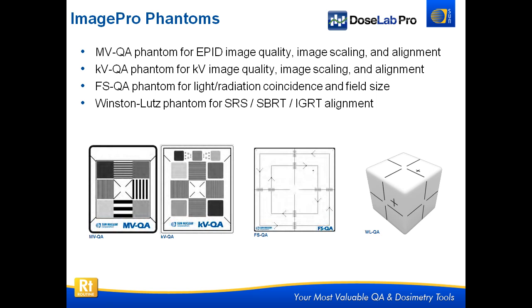We also have a Winston-Lutz Phantom for SRS, SBRT, or IGRT alignment. The cube has an embedded tungsten sphere in it. You can use it as a normal Winston-Lutz phantom, or you can do a CT scan of it, treat it just like a patient, pull it into your planning system, contour the ball as your tumor, and put that on your table to do a full cone beam CT. Using the offset alignment marks, you can align it in the room, have your cone beam CT system bring the ball to isocenter, then take two MV images to do a Winston-Lutz test — giving you complete end-to-end accuracy for how accurate you are positioning your SRS or SBRT patients.